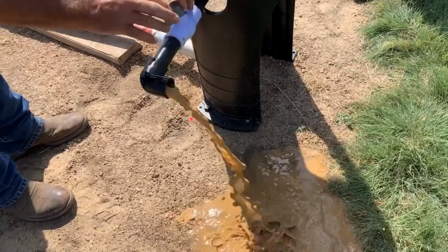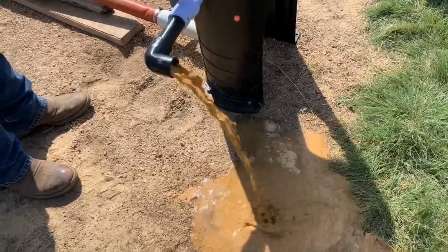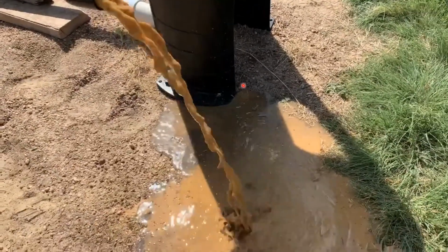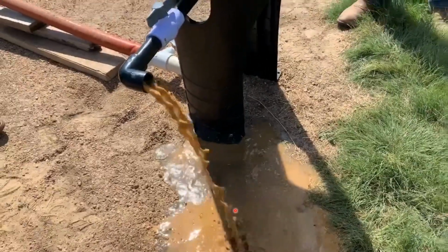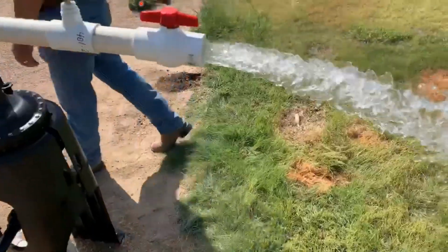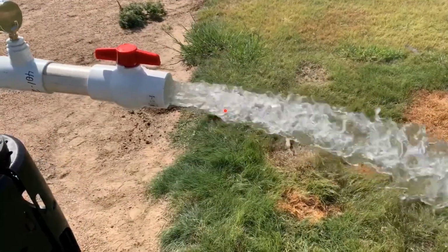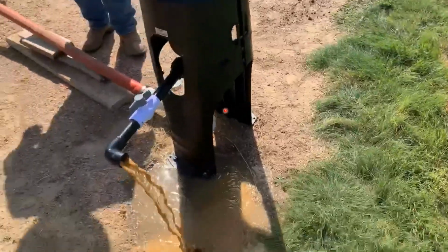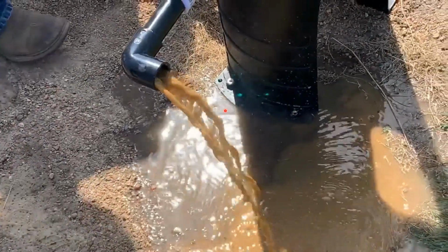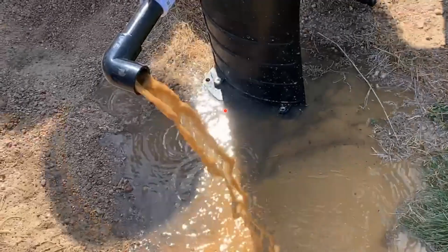So here's the purge. The water comes into the bottom of the separator. Okay. You can see there's a lot of silt here. The water comes in from the bottom, goes up through the top and out. Now we're showing continuous purge here because we want to do the compare and contrast. Now this is operating at about 1 psi differential.